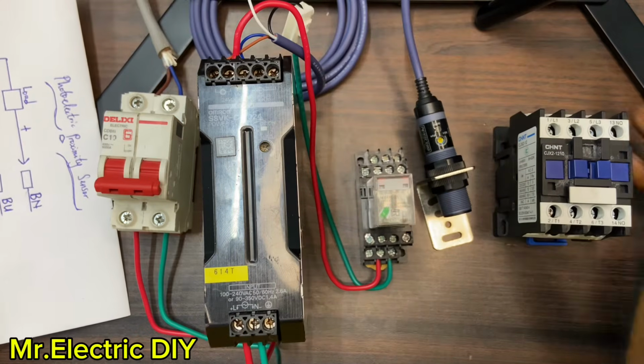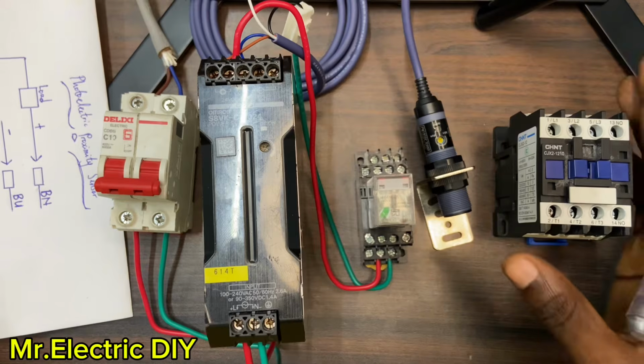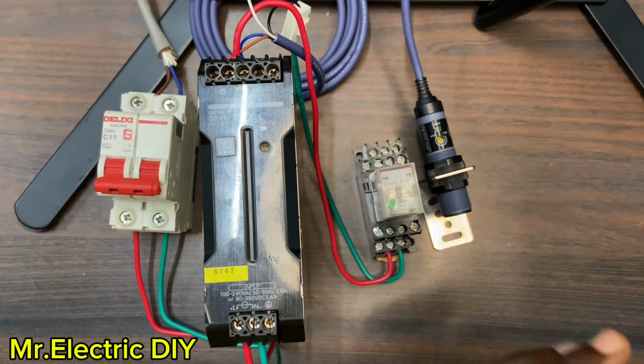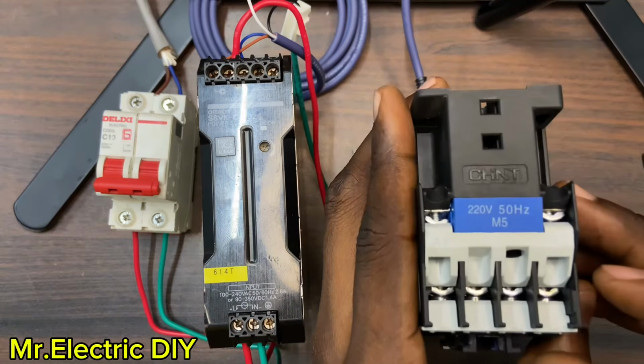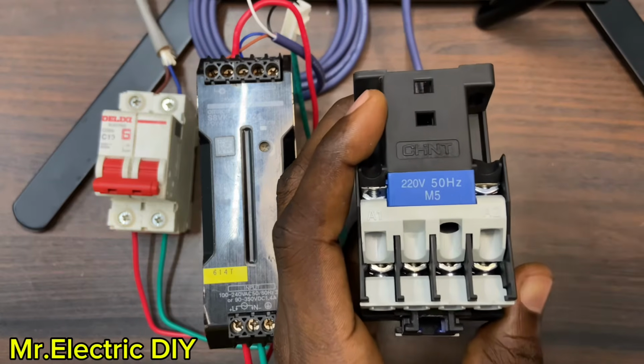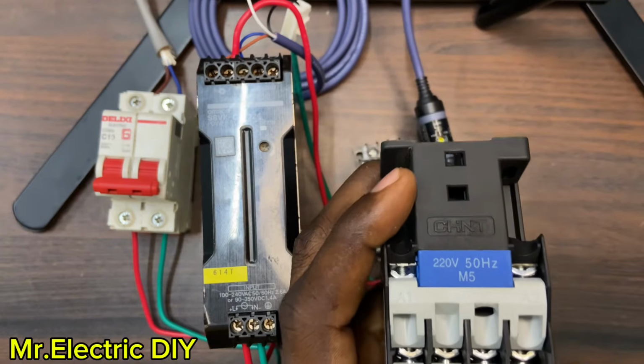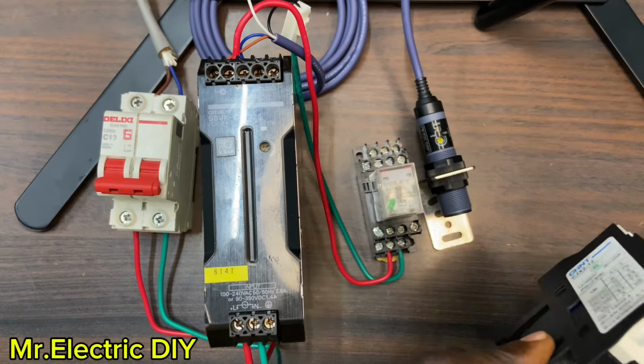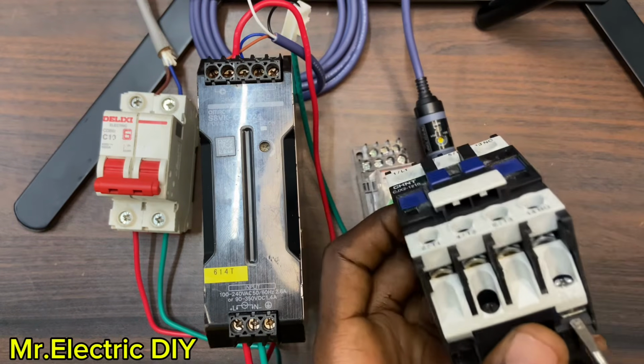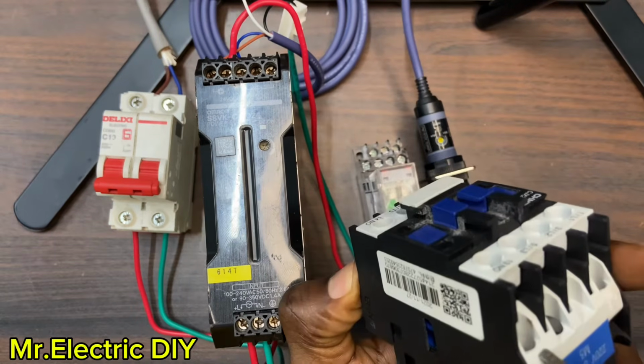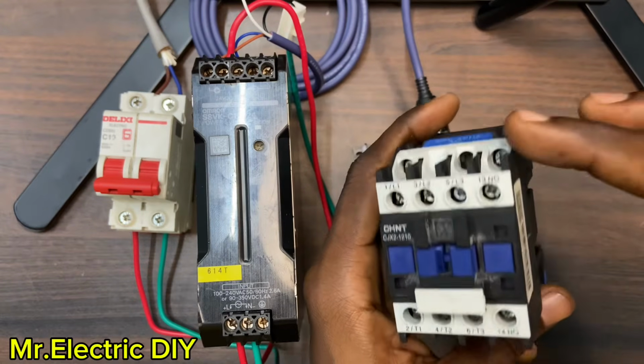So guys, let me connect the magnetic contactor to the circuit. This is a 220 volts magnetic contactor, and before a 220 volt load works, there must be live and neutral. So what I have to do is connect the neutral to A2. You have A2 at this side and another A2 at this side. These two A2 are linked together.